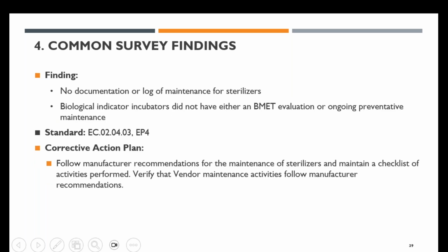Moving on to the next one, which is more on your sterilizers. Depending upon the type of service model you have in place, if it is maintained in-house, make sure you have documentation that complies with the manufacturer recommendations and all the safety checks as per the manufacturer requirements. That is really critical, which we have noticed in the last few years, especially on sterilizers.